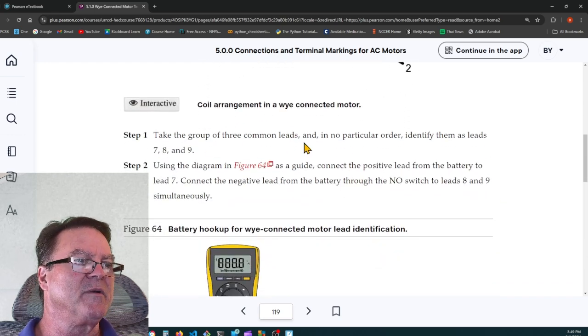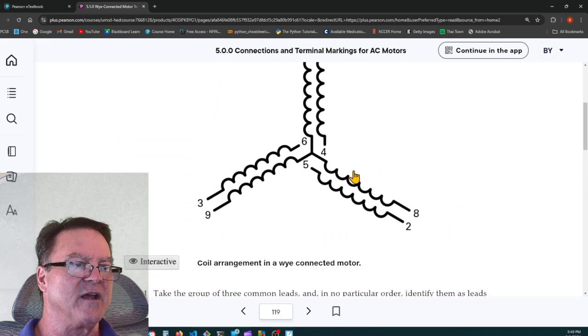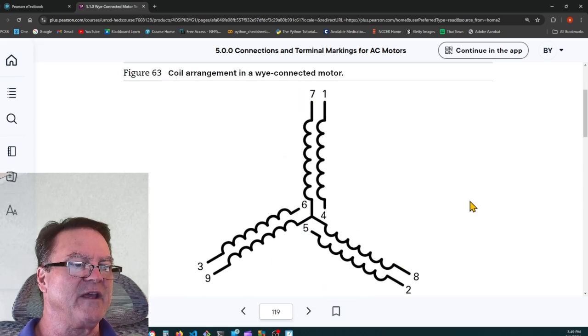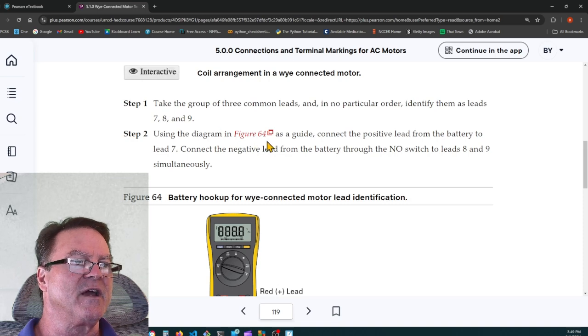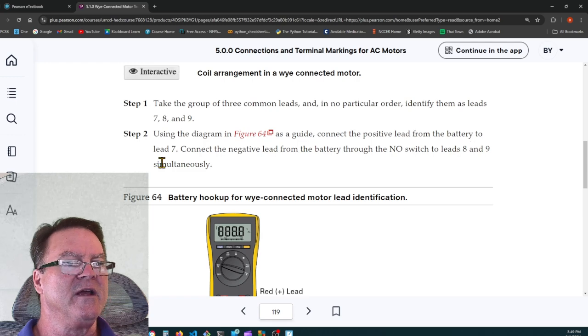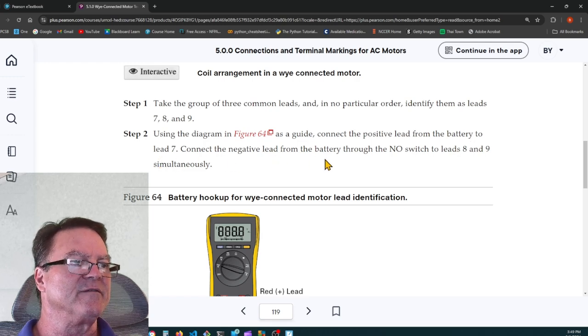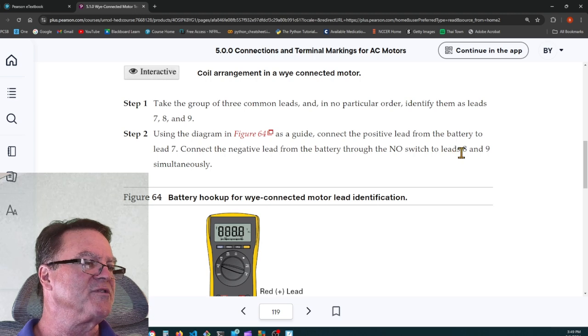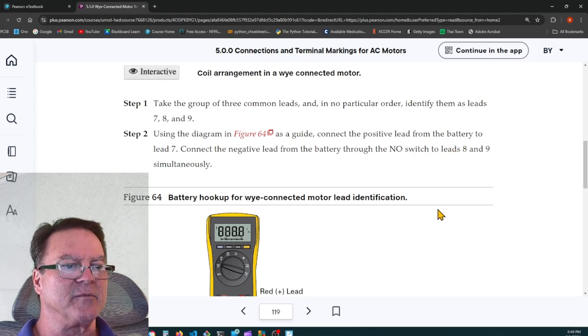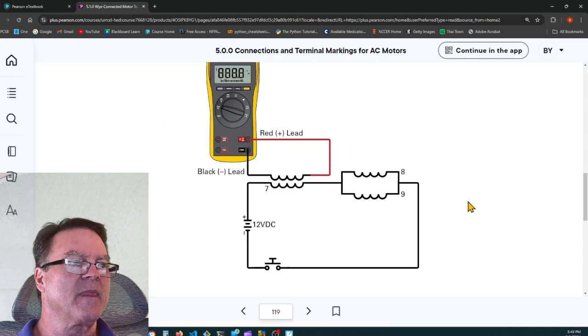Take the group of three common leads and in no particular order identify them as leads 7, 8, and 9. So the three that had continuity, we're going to designate them as 7, 8, and 9. Using the diagram of figure 64 as a guide, connect the positive lead of the battery to lead 7. Connect the negative lead from the battery through the normally open switch to leads 8 and 9 simultaneously. So there's 8 and 9. And there's their momentary switch.